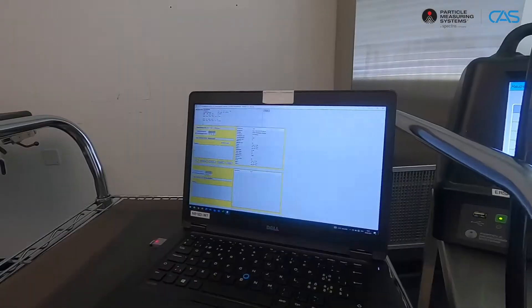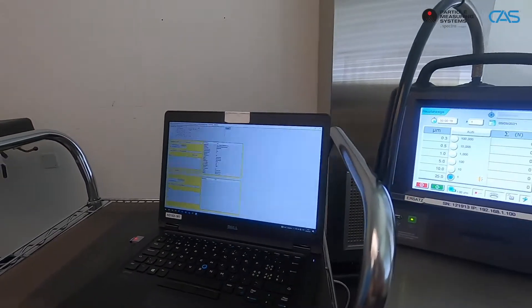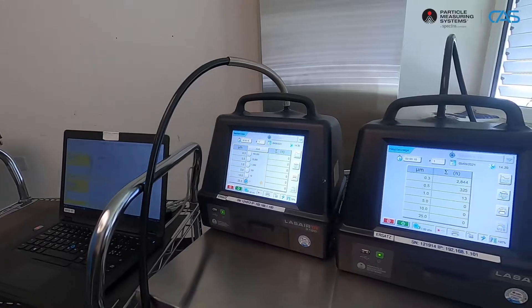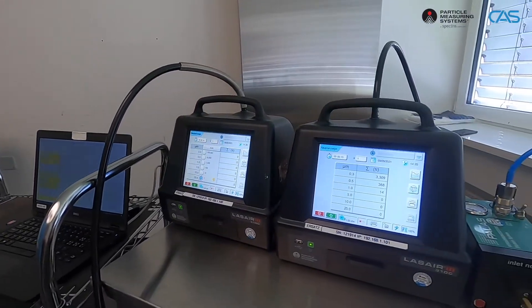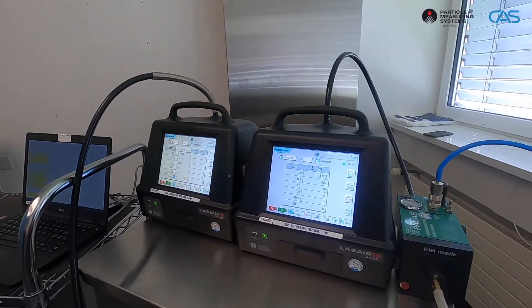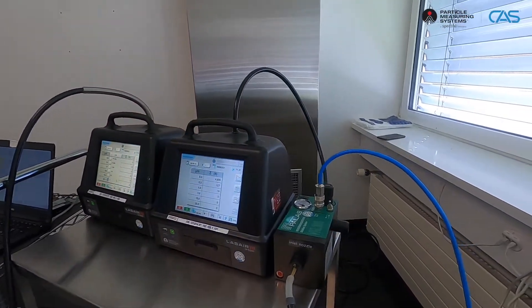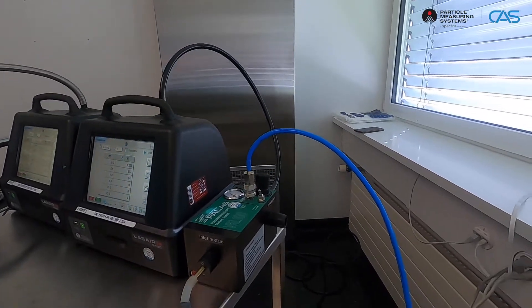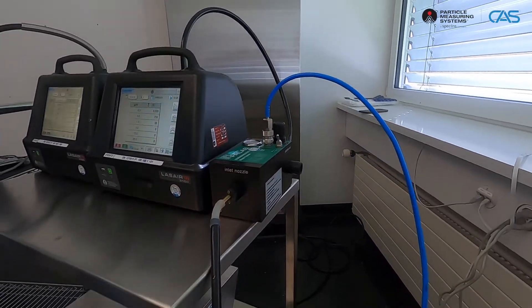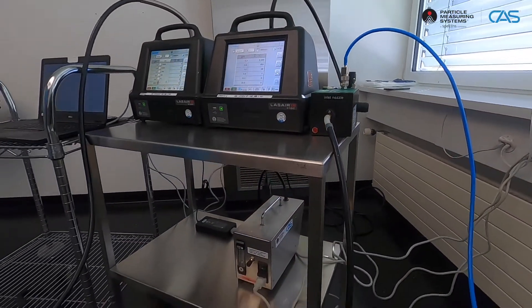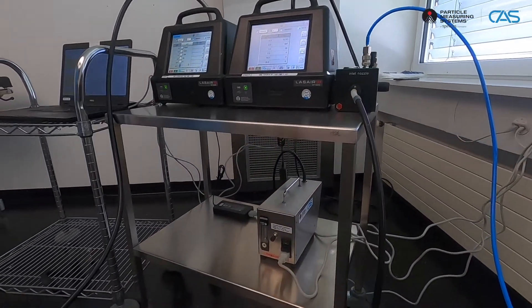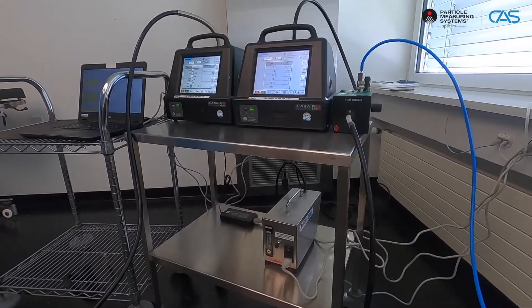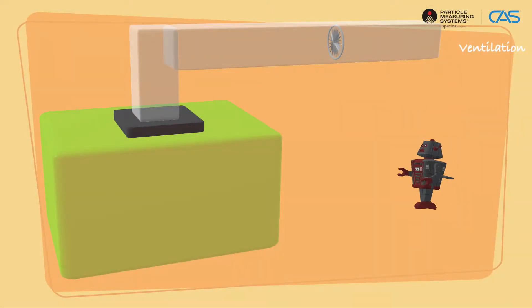To carry out the test, you ideally need a laptop with special software to read out and evaluate the measured values, two laser particle counters, a dilution stage with a dilution factor of 1 to 100, as well as an aerosol generator.